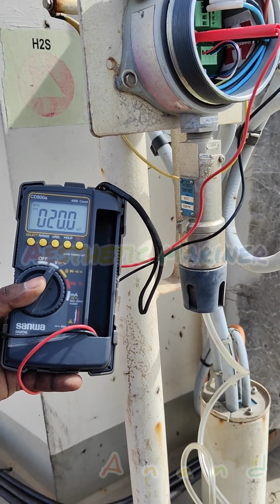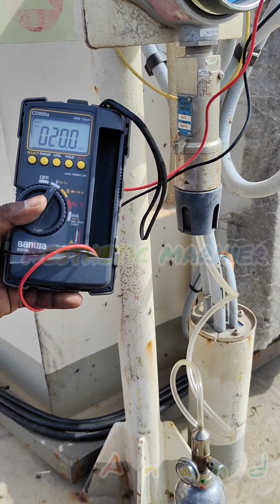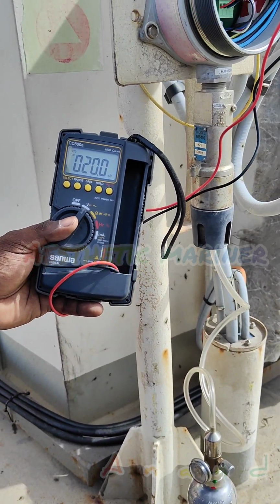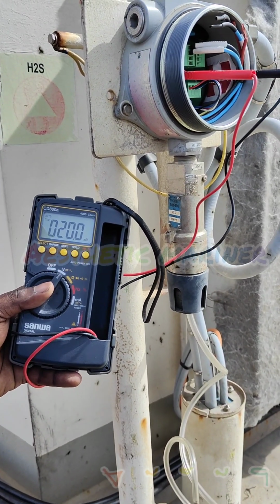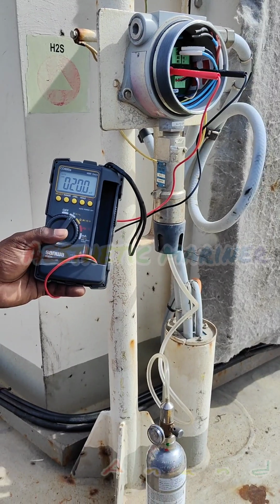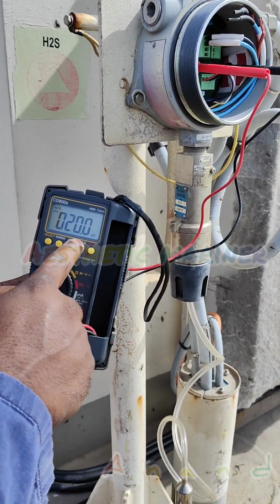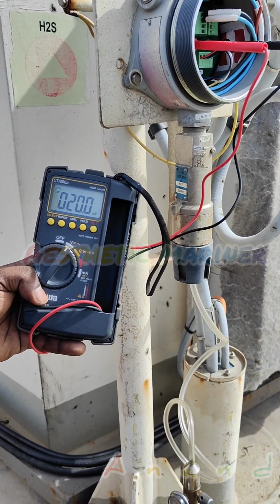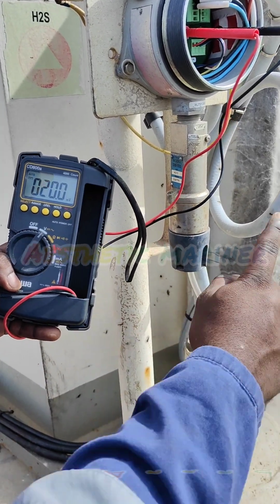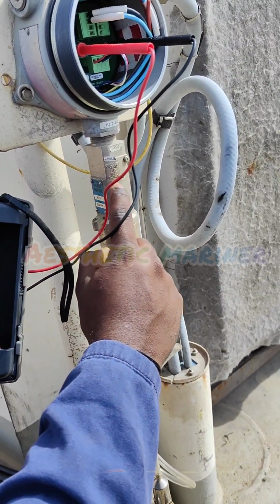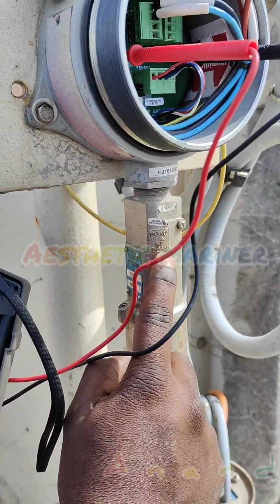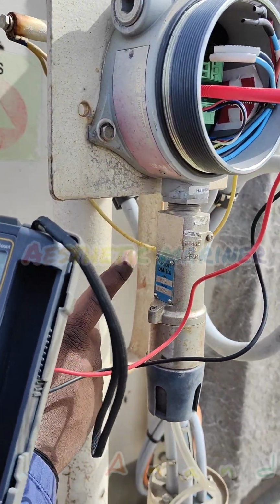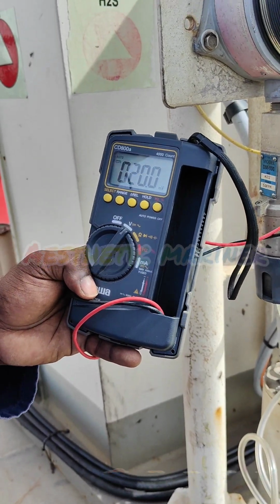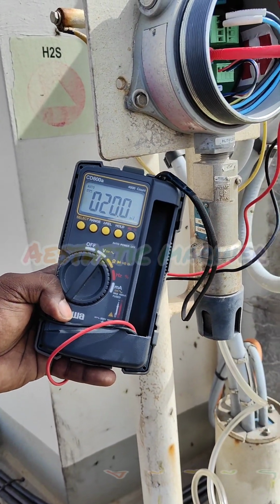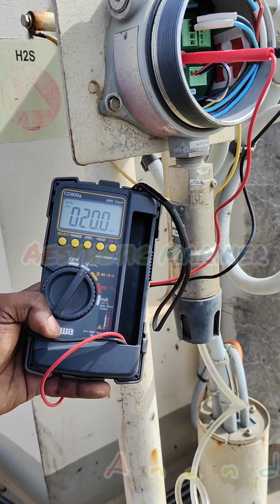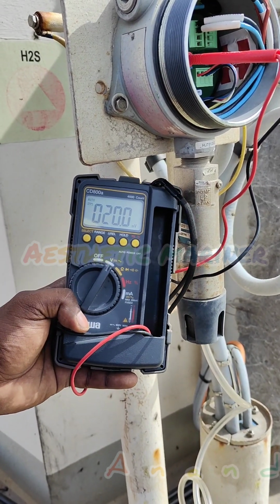After 2 minutes, the gas reading will come on the multimeter. For 25 ppm H2S, it will show 80 millivolt. If it comes less or more than that, we can adjust through program 1 and program 2. If we press the tab on program 2, it will increase, and if we press the tab on program 1, it will decrease. Like this we do the span calibration. Now we will wait for 2 minutes.